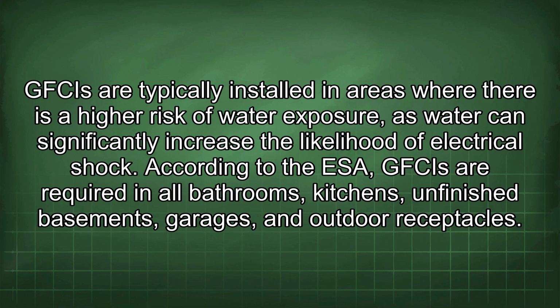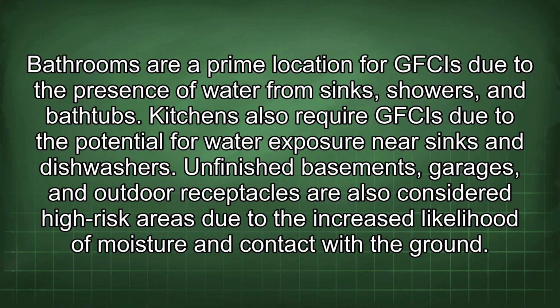According to the ESA, GFCIs are required in all bathrooms, kitchens, unfinished basements, garages, and outdoor receptacles. Bathrooms are a prime location for GFCIs due to the presence of water from sinks, showers, and bathtubs. Kitchens also require GFCIs due to the potential for water exposure near sinks and dishwashers.